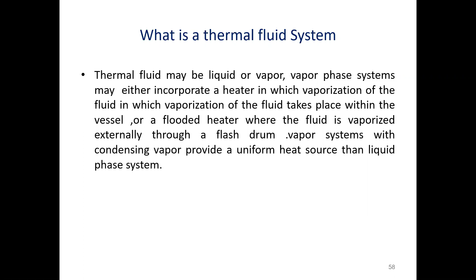The thermic fluid heater is normally operated below the boiling point of the thermal oil. As mentioned, thermal oil is used as a medium to absorb heat from the source and provide the heat to the liquids. That temperature is below the boiling point of the thermal oil. The oil in the thermic fluid system must have a higher boiling point, and only then can it be utilized.